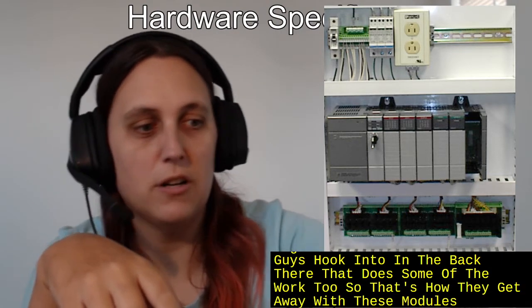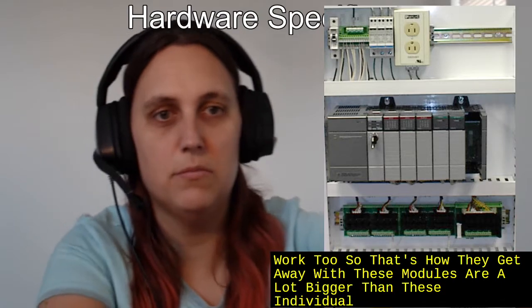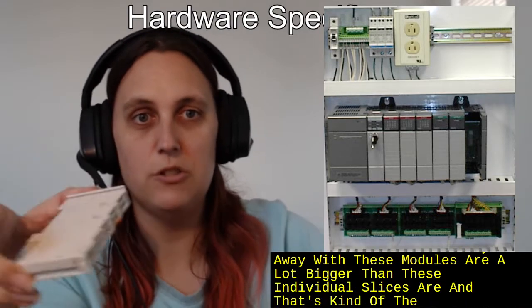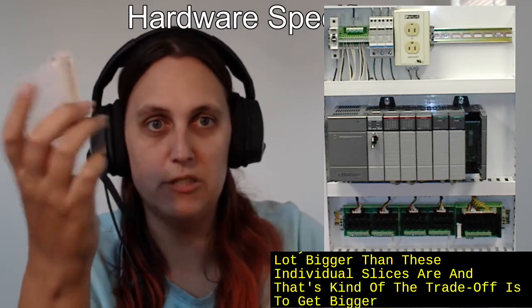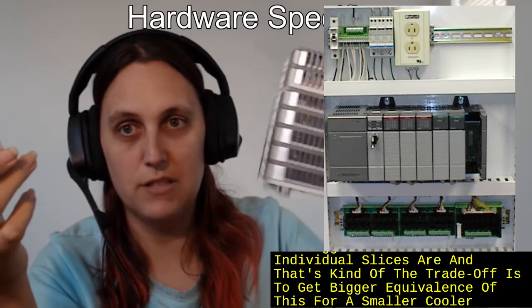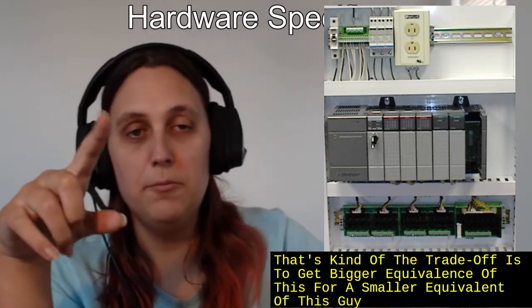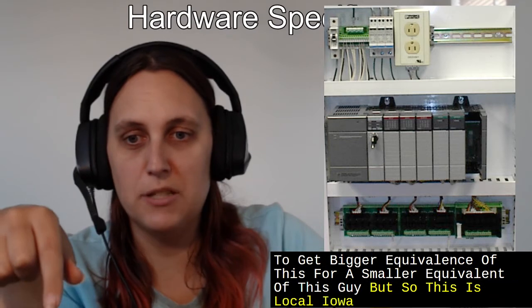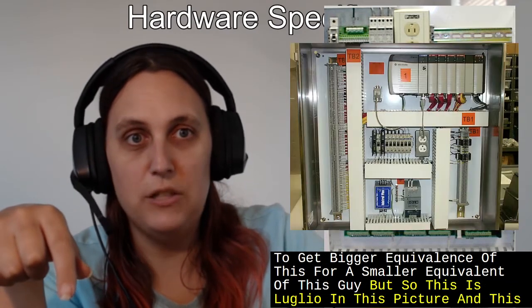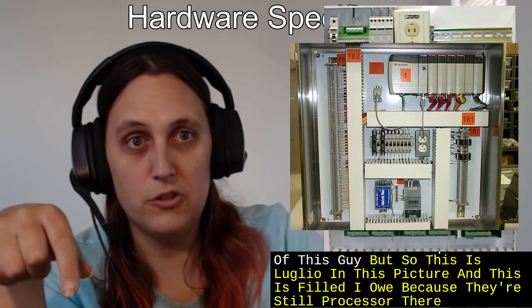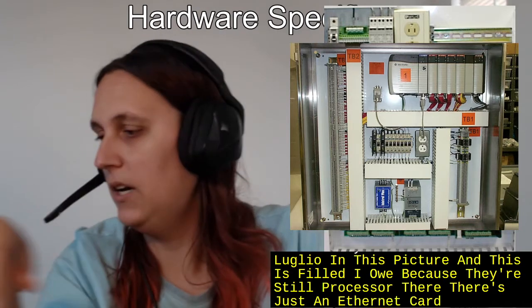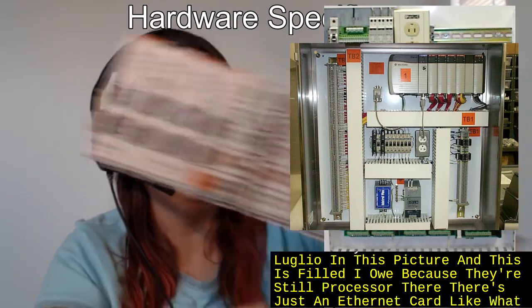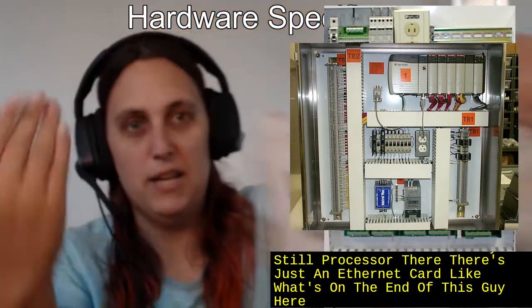These modules are a lot bigger than these individual slices are, and that's the trade-off: you get bigger equivalents of this for a smaller equivalent of this guy. So this is local I/O in this picture, and this is field I/O because there's no processor there. There's just an Ethernet card, like what's on the end of this guy here, to connect it back to wherever its processor lives.